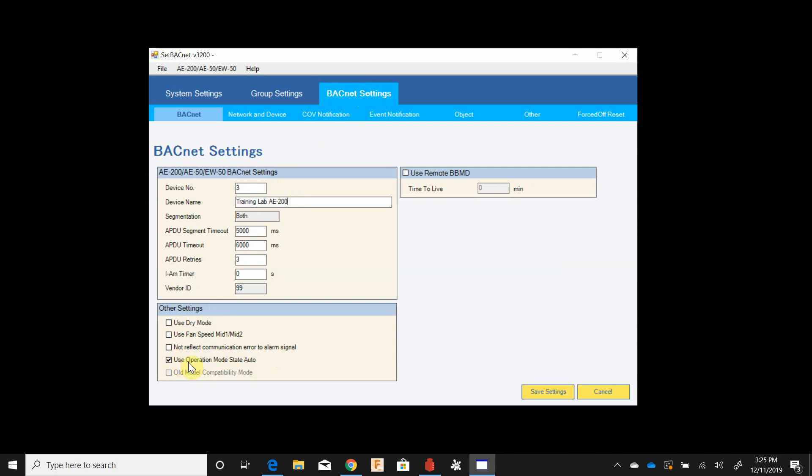This box is use operation mode state auto. What this does is the BMS system is going to send a mode setting and then they're going to read back what's on the thermostat. If this is unchecked, when they send auto they'll read back either heat or cool depending on which active mode the thermostat's in, even though it's still auto at the thermostat. If this box is checked they'll send auto and they'll read auto, so they can know that the thermostat is actually set in auto mode. This is a preference on what they would want, so ask this during the integration.